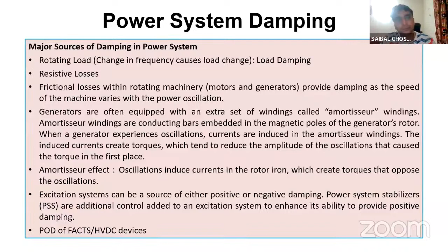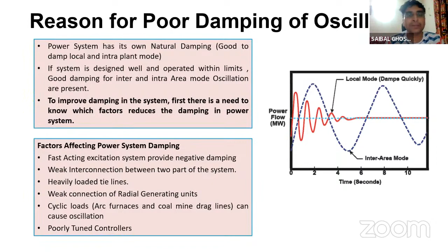Now, why is the power system poorly damped, or what affects the damping of the power system? That has been explained piecewise previously: a fast acting excitation system can provide some negative damping, weak interconnection, heavily loaded tie lines. All these are root causes of poor damping of oscillation in the system. Poorly tuned controllers are also a reason, or we can say they are a tool which can be used to improve your damping. When they are not properly tuned, they cause poor damping, but if they are properly tuned, they can provide good damping in the system.